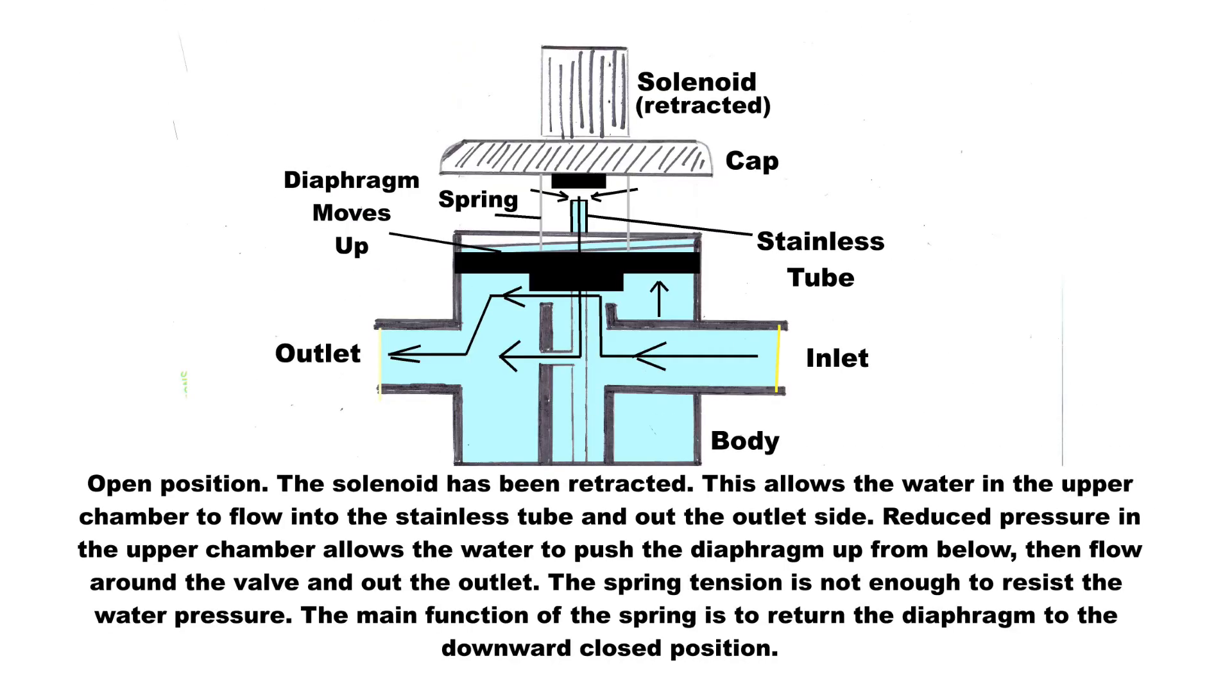Here's the open position. The solenoid has been retracted. This allows the water in the upper chamber to flow into the stainless steel tube and out the outlet side. Reduced pressure in the upper chamber allows the water to push the diaphragm up from below, then flow around the valve and out the outlet.